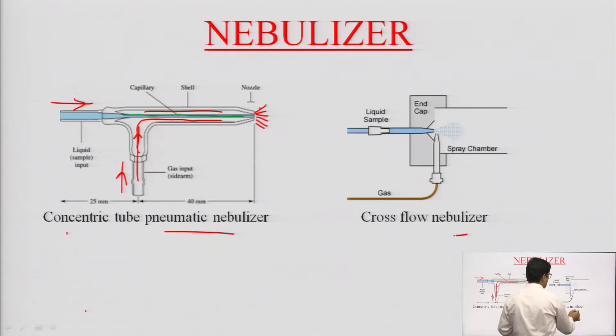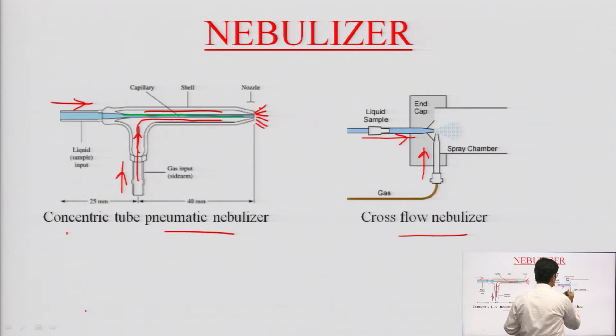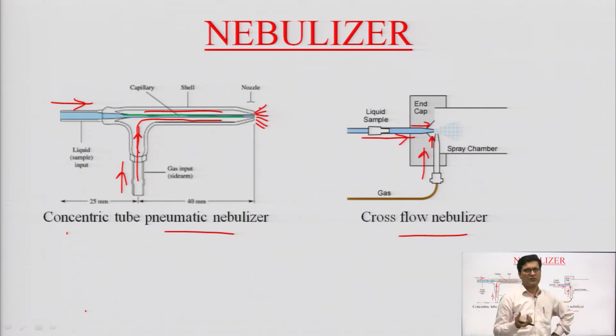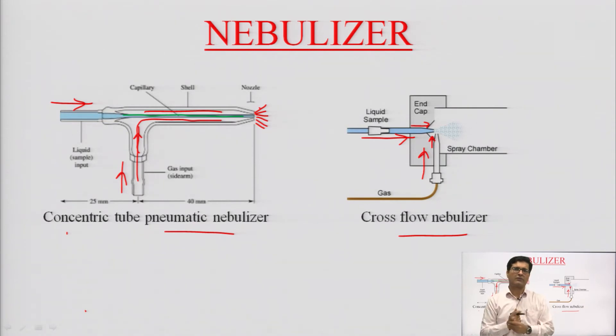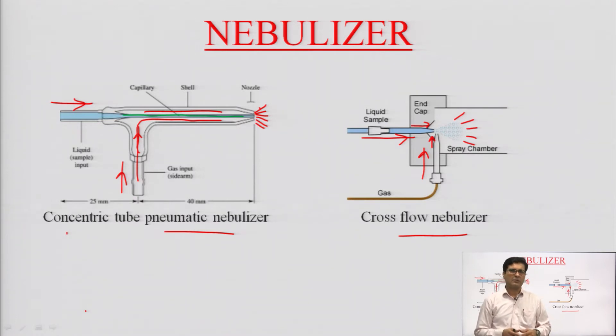In the cross-flow nebulizer, the sample liquid and gases do not travel parallel to each other but move perpendicular to each other. The sample liquid entry point and the high-pressure gas entry point are at right angles. As the liquid crosses the gas stream at a right angle, it distributes into fine droplets, and a spray of fine droplets is observed in the chamber. Both types of nebulizers work differently, but the ultimate goal is to obtain fine droplets of sample so they can be easily evaporated and vaporized in the burner.